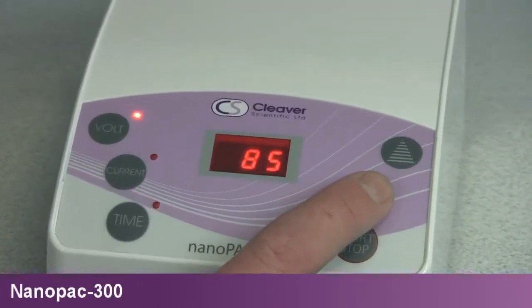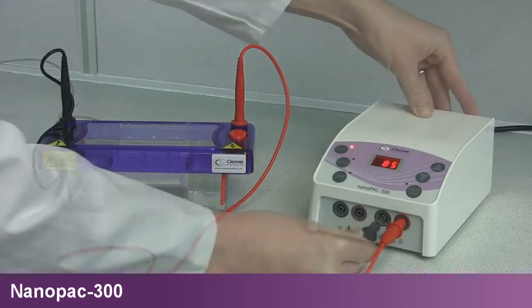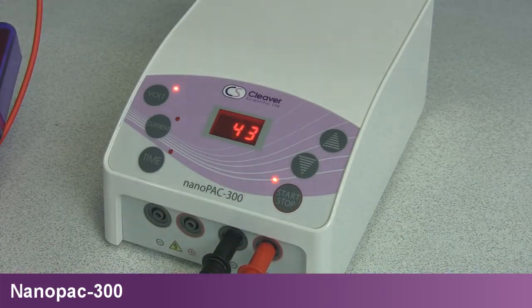The NanoPak 300 Mini is the smallest power supply within the omniPAC range. With maximum 300V and 400mA constant voltage and current outputs, the NanoPak 300 is capable of running Cleaver Scientific horizontal multi-sub and vertical OmniPage mini systems.